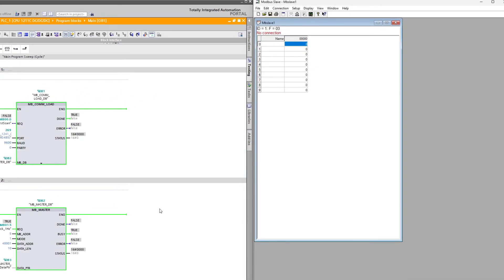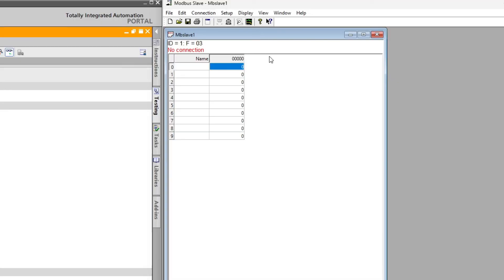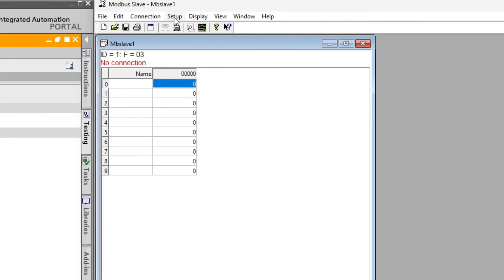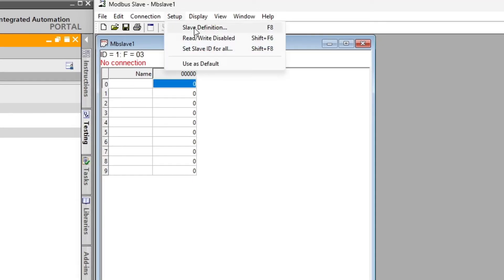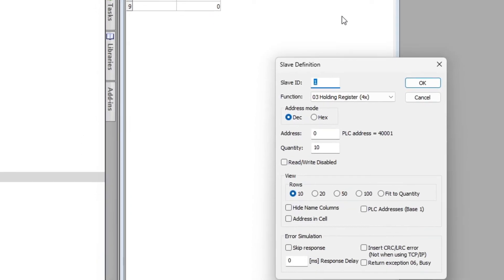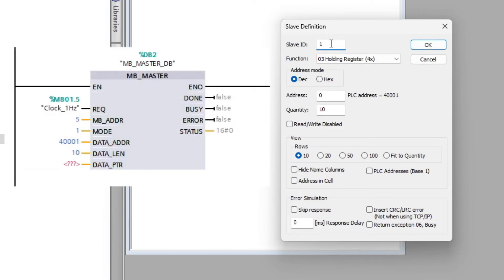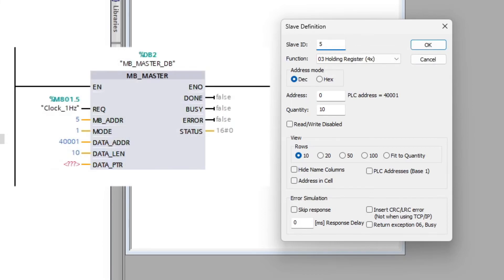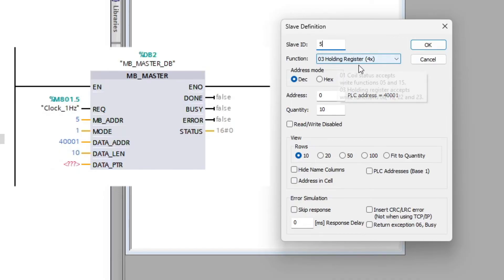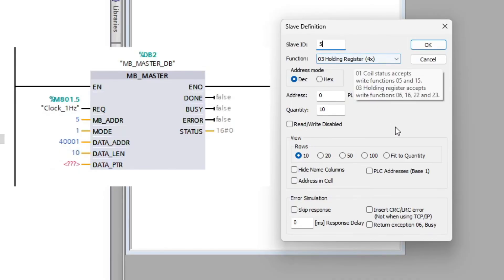In the Modbus simulator we want to go to setup and click on slave definition. Here we want to write the slave ID, which is the same as the master block's Modbus address input. The function tab should be set to holding register, which have the same data address as 40001. And we want to write a data length from 0 to 10.